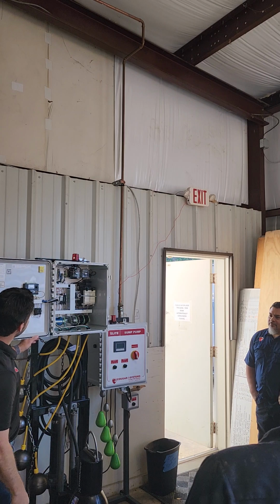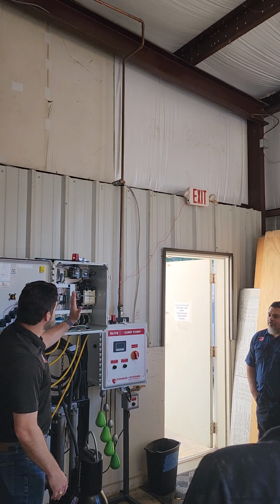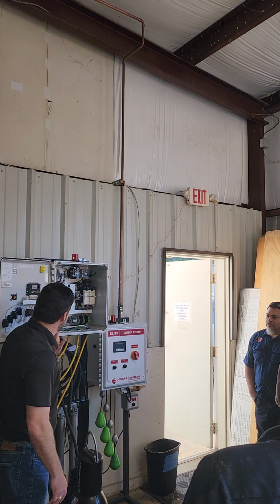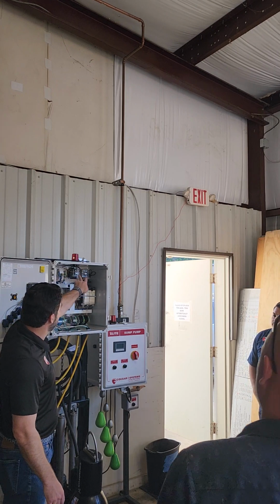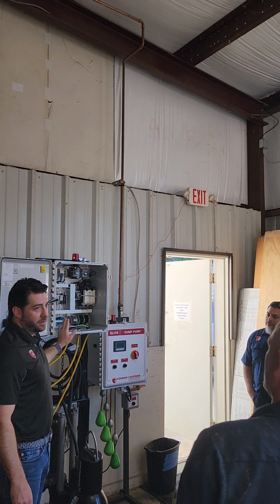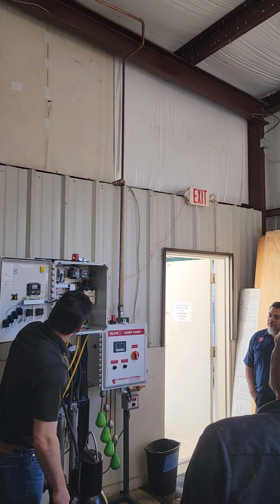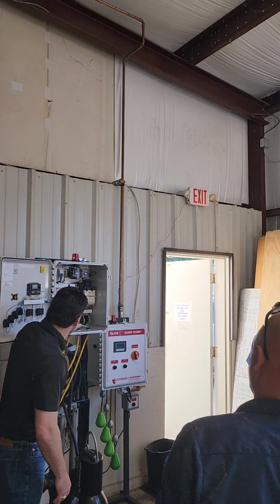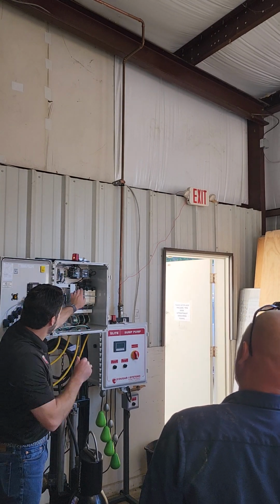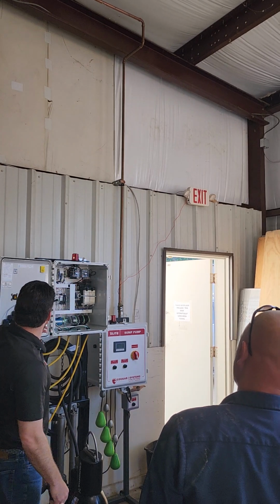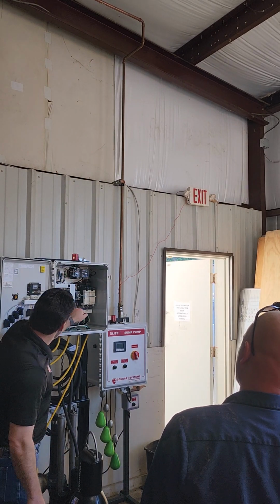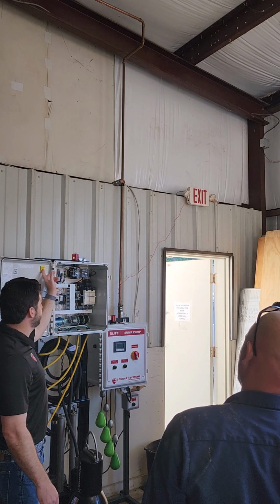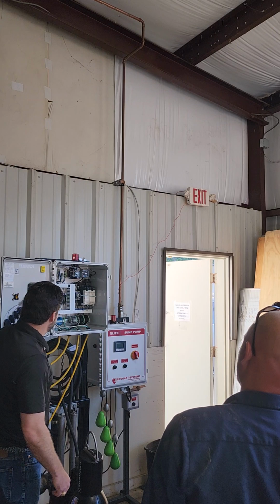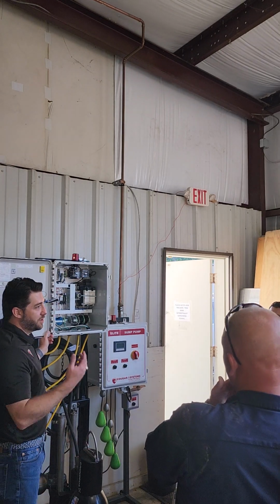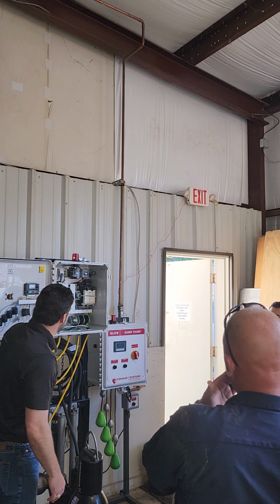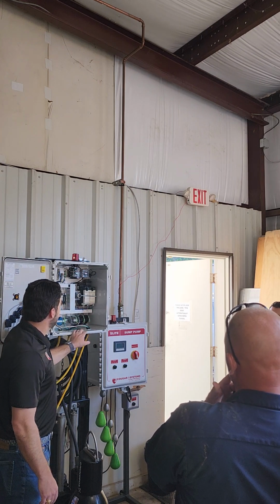So on the inside of the panel, we have the same kind of configuration. The high voltage on the right, the low voltage on the left. The difference here is that after we go through the control transformer, now we have some additional stuff going on in the control circuit because we have a PLC and we have some additional relays and fuses to protect it. So we got fuses here on the control transformer that are on the door, hopefully. Yes, these are. And then we have some additional fuses that protect the PLC touchscreen here. Okay, so that's back to that same thing. If you have power coming in, but you don't have control power, fuses are going to be a good spot to start. A little bit different, kind of motor starters here.